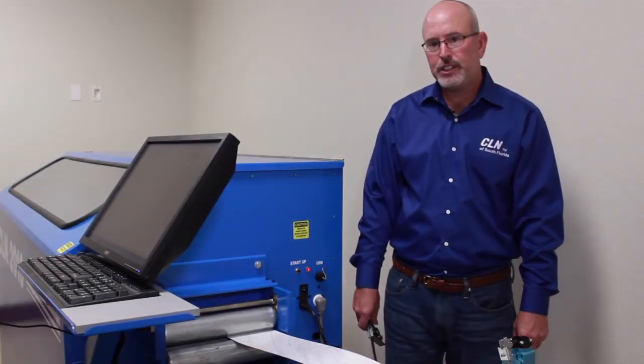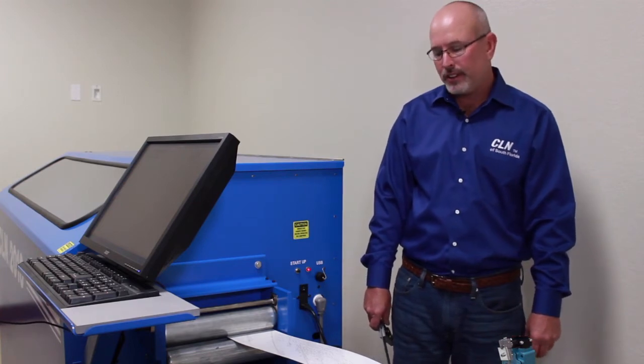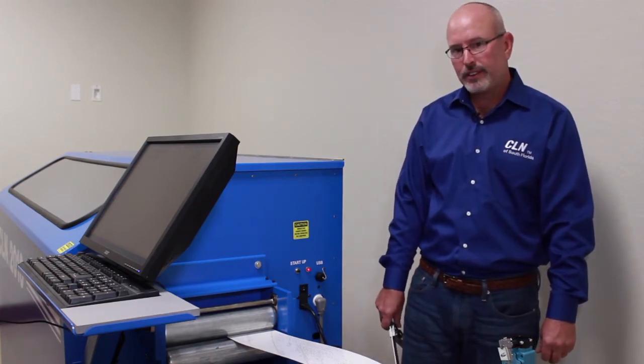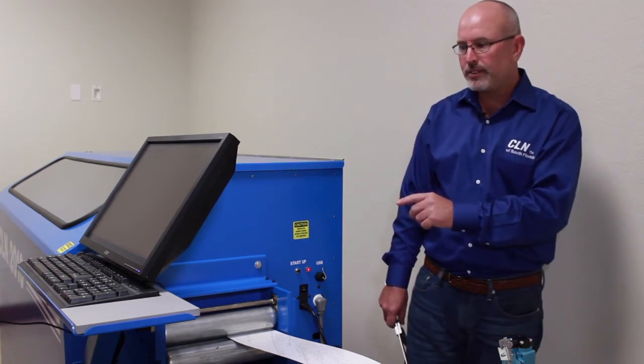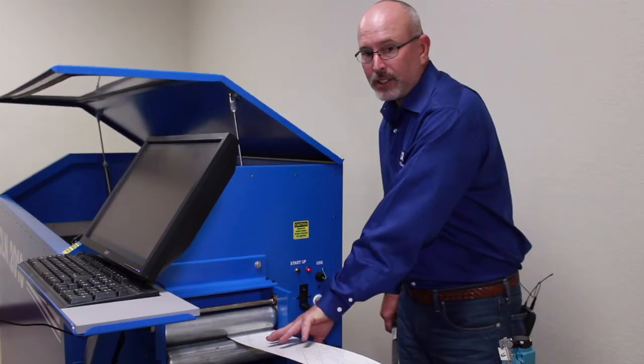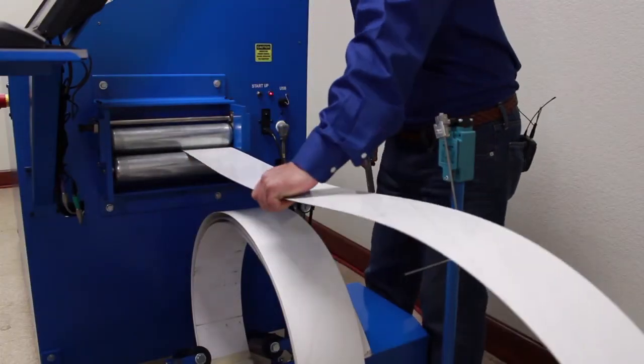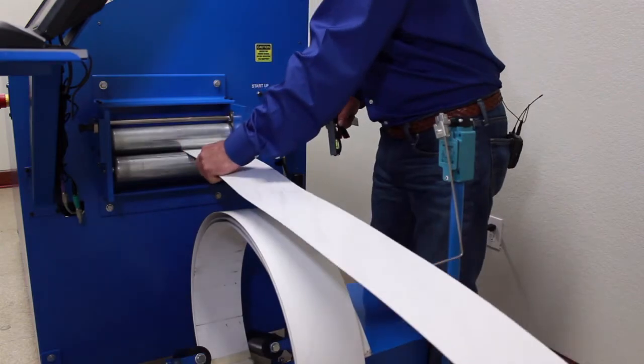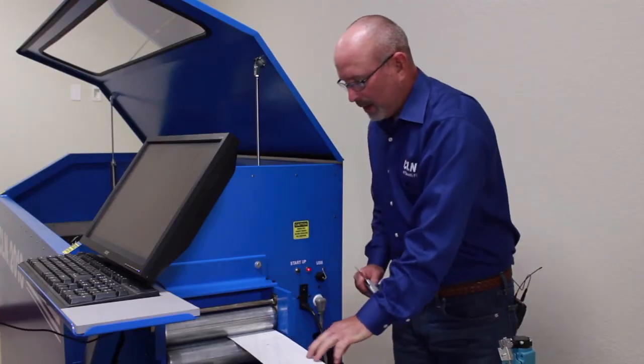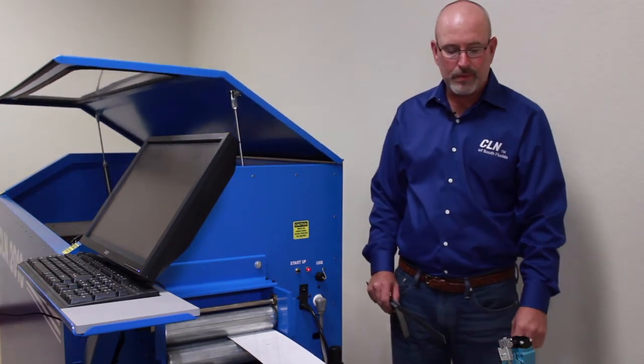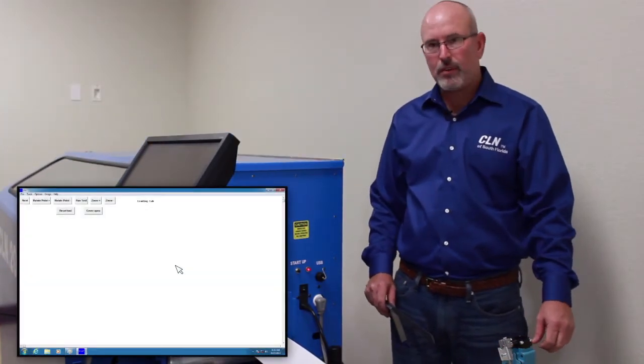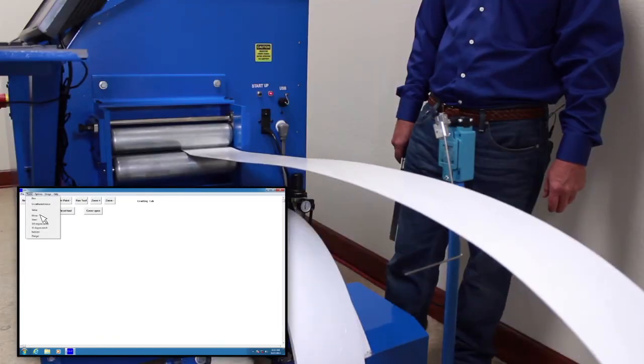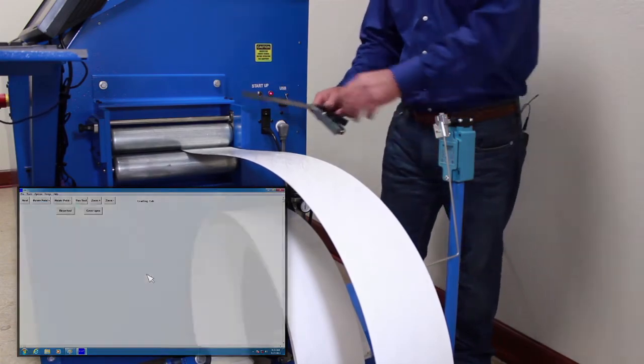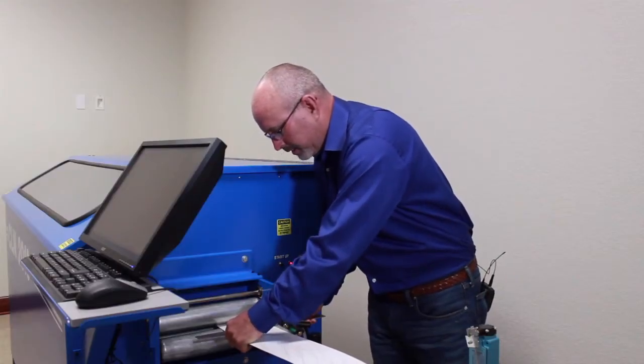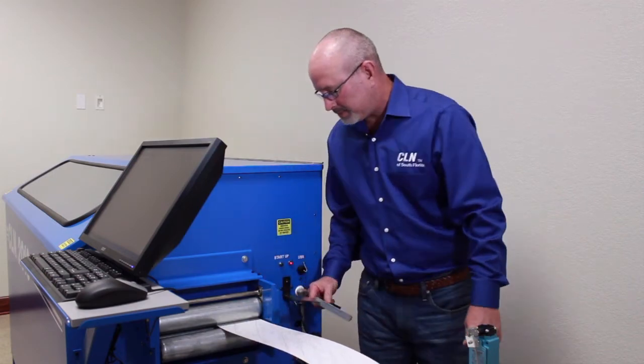Now that we just made a change in the software, we're going to test to see if the change we made is correct. So the first thing we're going to do is open the cover and pull the material back to our first mark. Okay, now we're going to close the cover and we're going to make the material move 48 inches and test to see if the material moves exactly 48 inches. And we're exactly where we need to be. We moved exactly 48 inches.